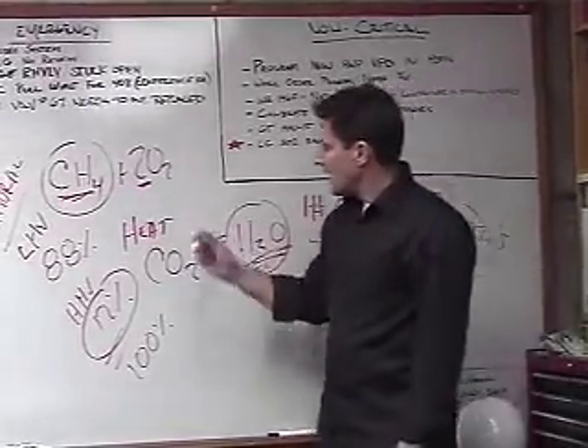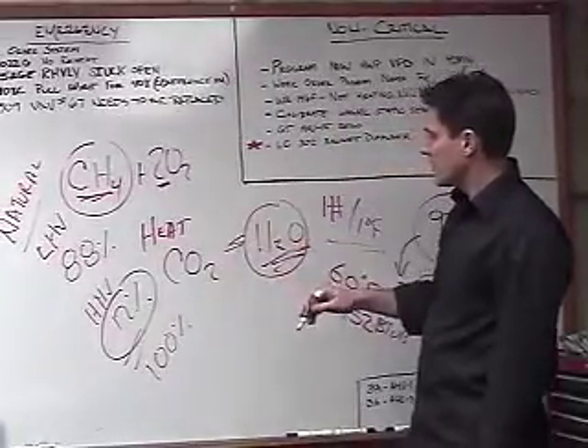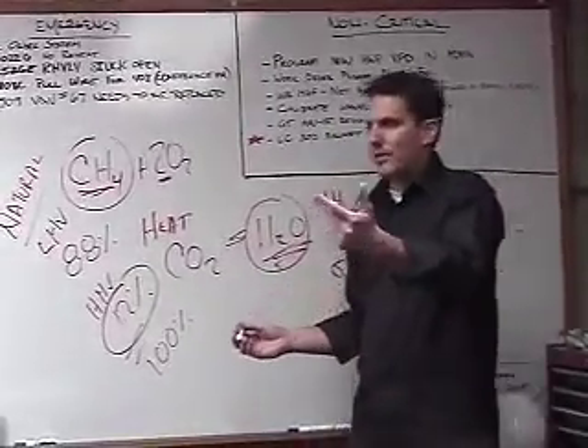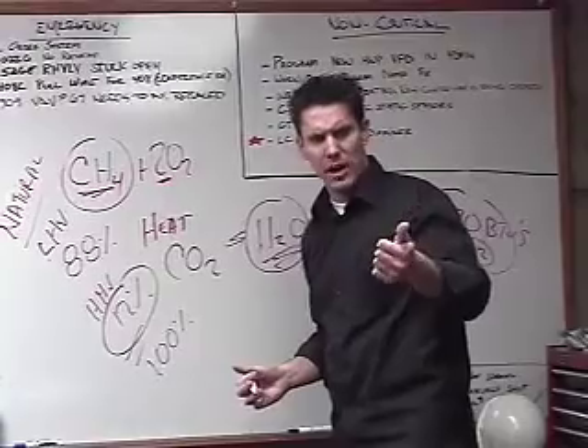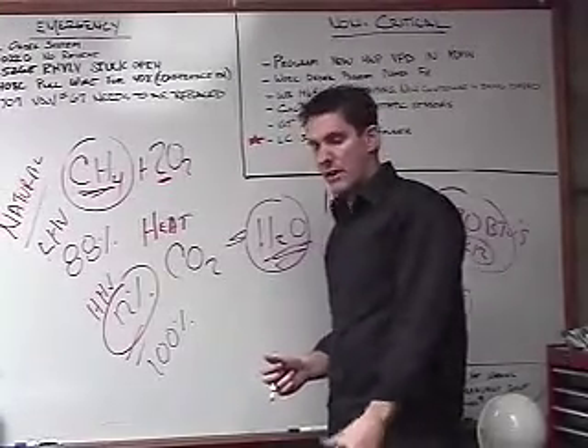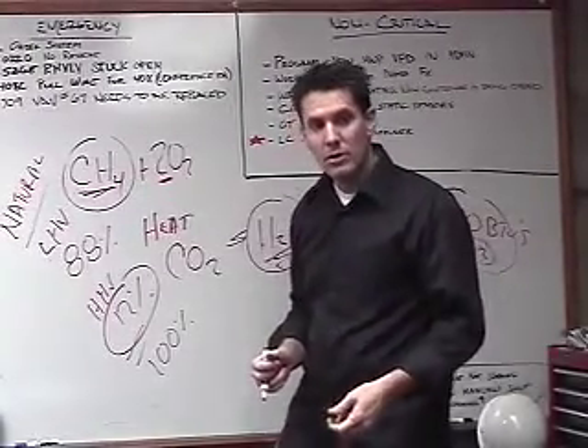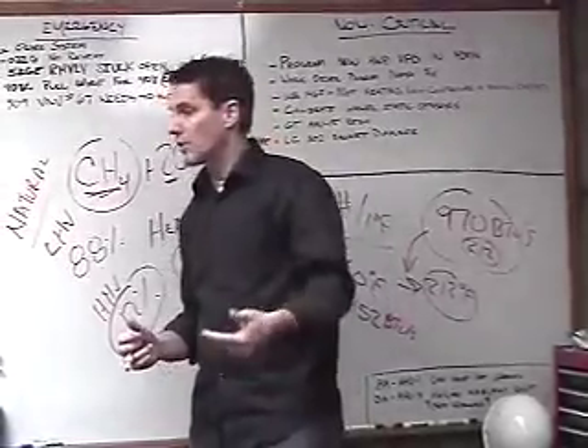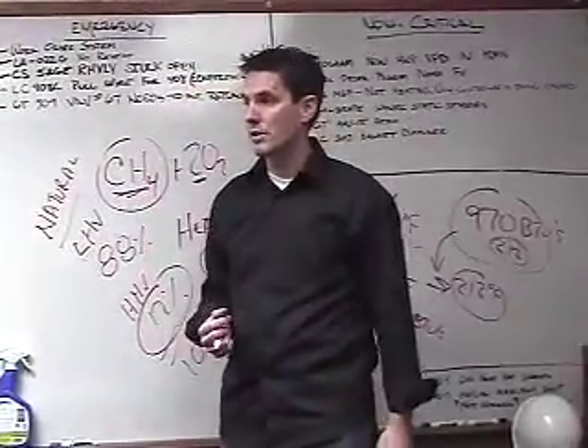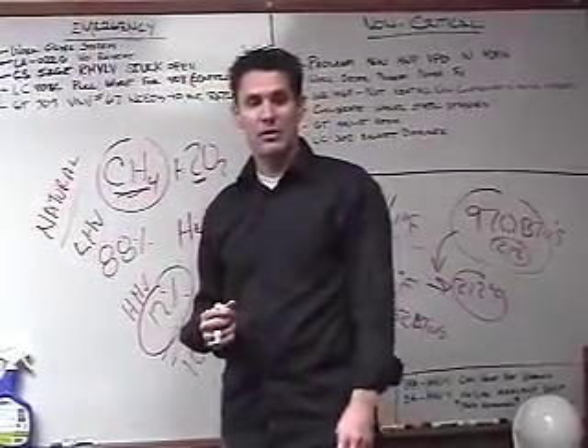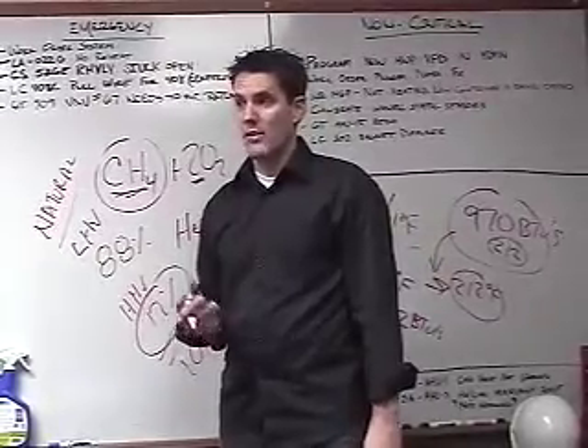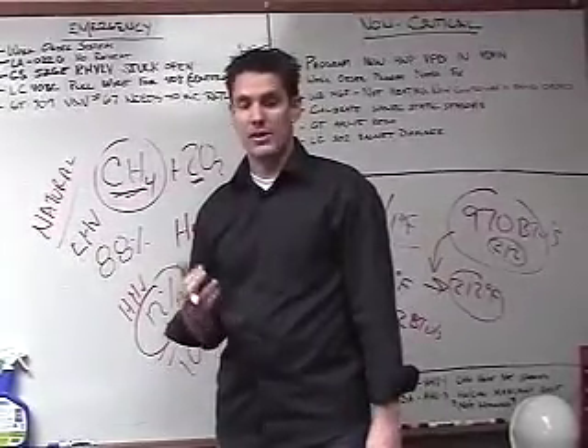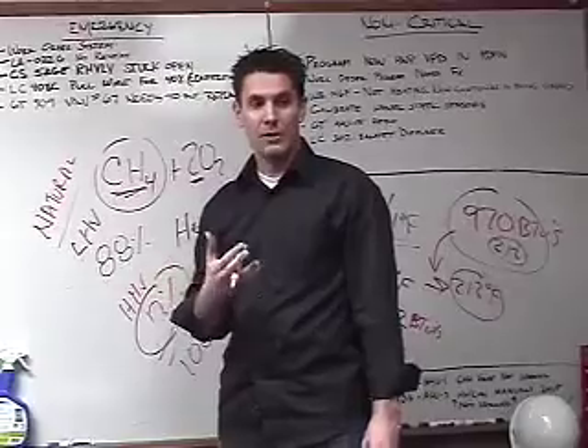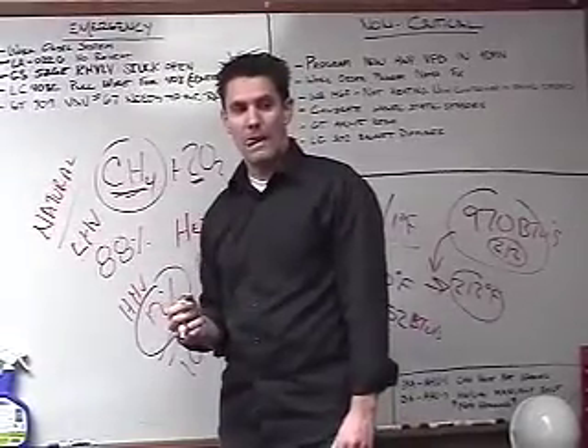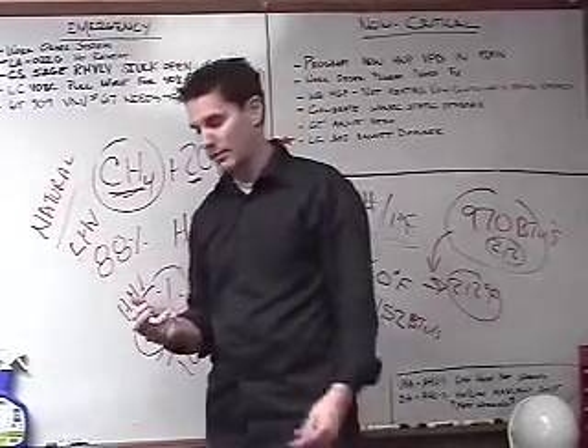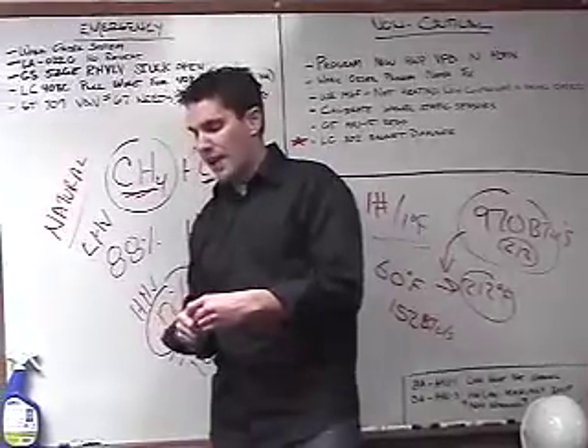Okay, so a condensing boiler, with the process of combustion, any boiler, you guys have water tube boilers, right? Don't you have some Bryans? Okay. Have you ever seen those tubes sweat? When you start up the boiler in the fall when it's cold, do you ever see condensate form on those boilers? Is it a condensing boiler? No. Have you had to replace your boiler tubes? Have you seen them rust out? Hopefully not. No. Okay, that's good. Any boiler will condense.